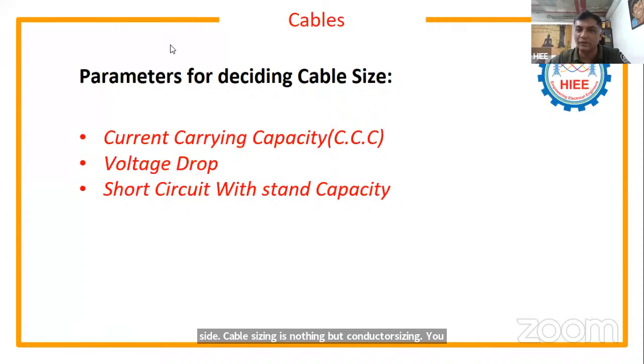You should not get confused. Cable is nothing but conductor with insulation. Here you are trying to find the cross-sectional area of the conductor based on the current carrying capacity. Okay, so the cable size depends on these three parameters: one is current carrying capacity, voltage drop, and short circuit withstand capacity. These are the three major parameters that decide cable size.